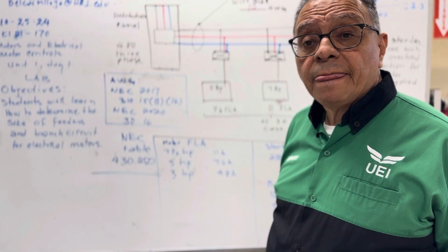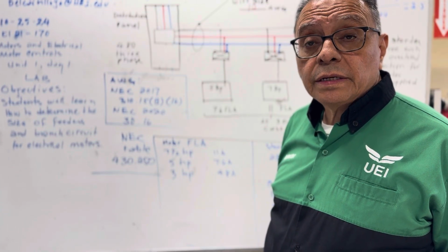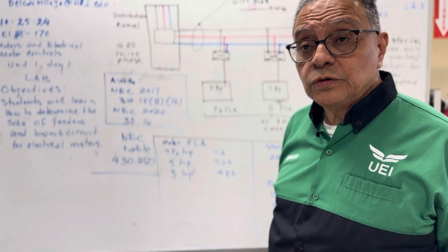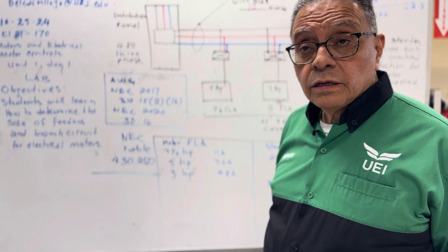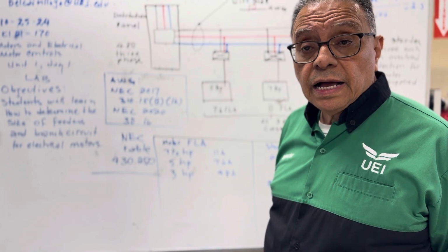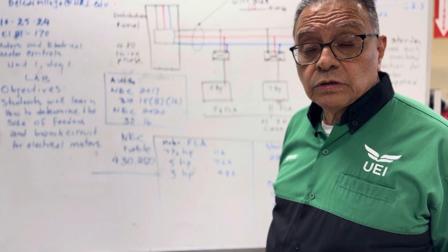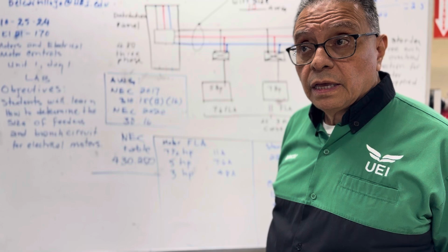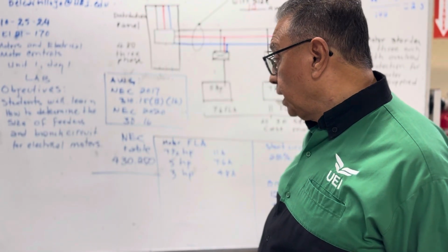Don't forget, this is based on the NEC. We are learning and practicing how to use NEC table 430.250 for three-phase electrical motors, and table 430.52 in order to determine the rating of my fuse, the short circuit protection.